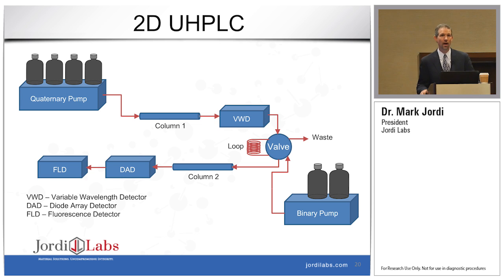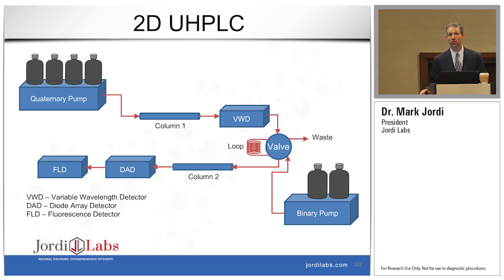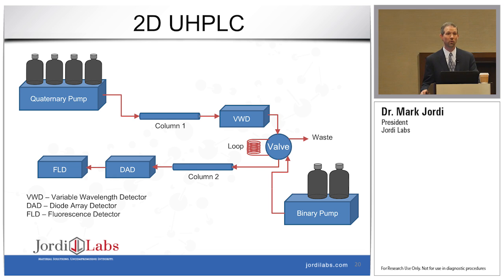I wanted to show you one example of some interesting work we've been doing recently on 2D UHPLC. When we get an extractables profile, particularly on a medical device or a complicated packaging system, there may be a large number of plastics involved, and sometimes we'll obtain extracts that have several hundred different constituents that we're tasked with quantifying. We've begun to rely heavily on 2D UHPLC for this. My instrumental setup has a quaternary pump in the first dimension going into a first column and then into a variable wavelength detector. We then have a valving system for hard cutting individual fractions or comprehensive cutting, which then feeds into a second column passing into either a DAD detector, fluorescence detector, or our QTOF system for further identification and quantification.